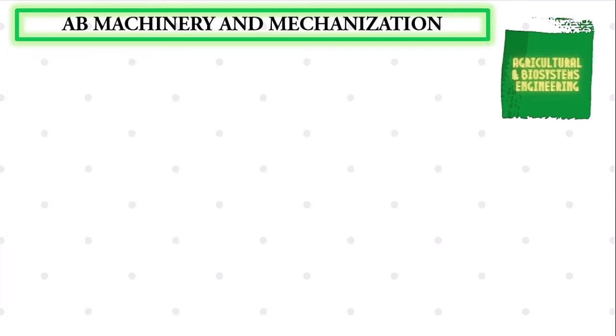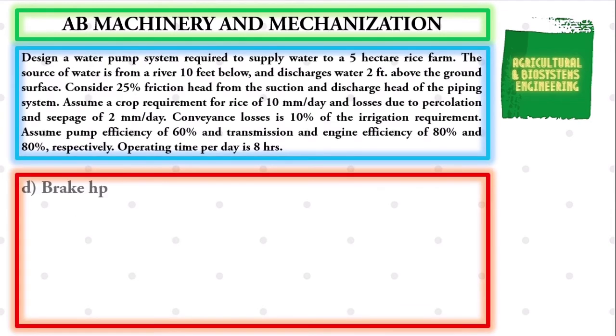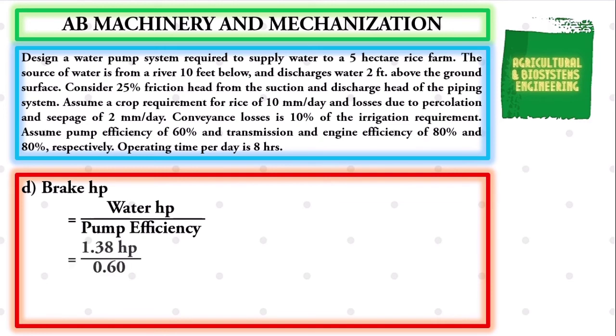The next value to solve is the brake horsepower. The formula is: Brake HP = Water HP ÷ pump efficiency. Substituting: 1.38 ÷ 0.60, giving us a final value for brake HP of 2.3 horsepower.